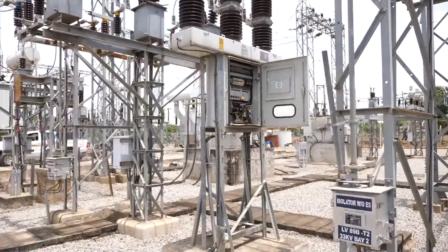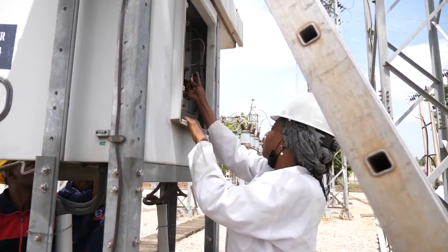He also said the TCN management has often worked towards clearing any challenge that could hinder seamless bulk power transmission from the substation. We don't have much challenges because everything has been arranged. Like you can see now, our maintenance men are on site, working in the switchyard. Our aim is to give them a protection guarantee. As they are working now, we have isolated the area where the job is to be done. The apparatus on which they want to work has to be properly isolated so that there will be no accident. Meanwhile, all the feeders on transformer TR2 are out, because there's no way you can close the feeders to feed the public while they are working there. It is only at the end of the maintenance work that they surrender the permit, authorizing us to bring back the equipment live again.